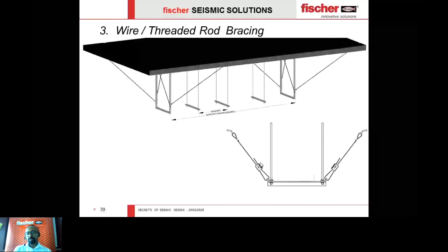You can convert a normal suspended system to a seismic system with the help of certain bracings. This is how it looks: a normal threaded rod support for a cable tray can be converted to seismic support by arresting the seismic forces on both sides or in 4 directions using these wires. Also, you can use threaded rods—we have a special system which can provide bracings using threaded rods.